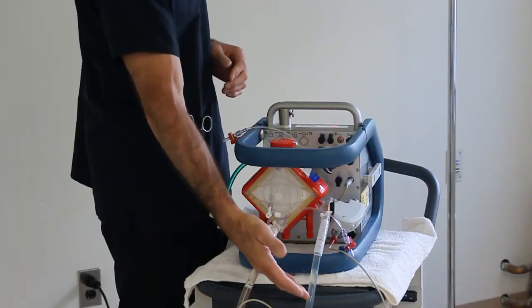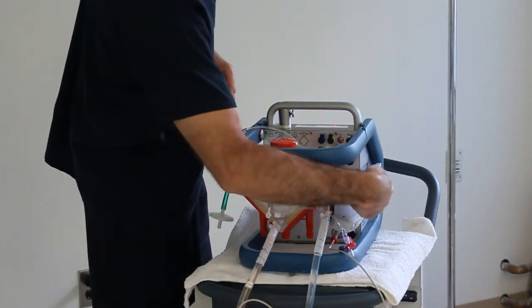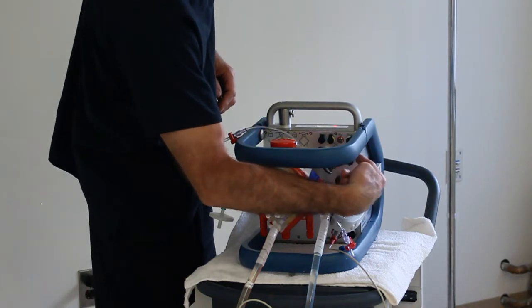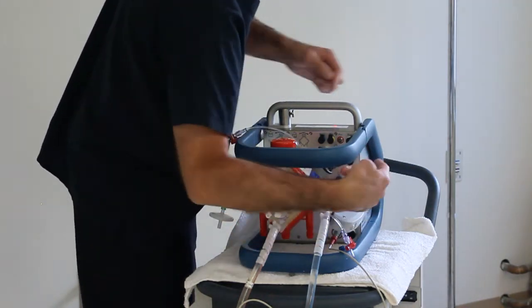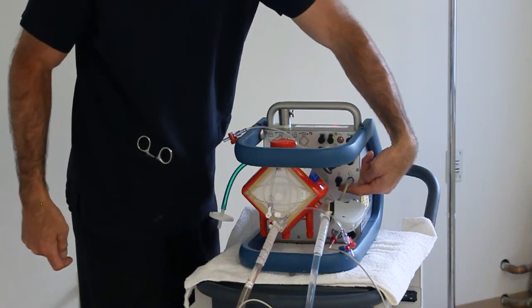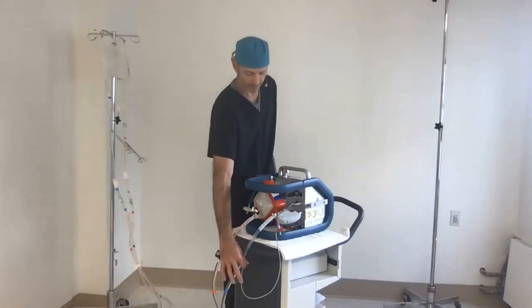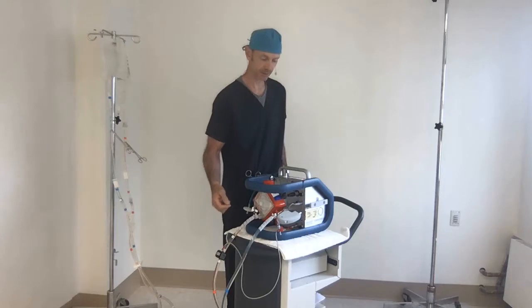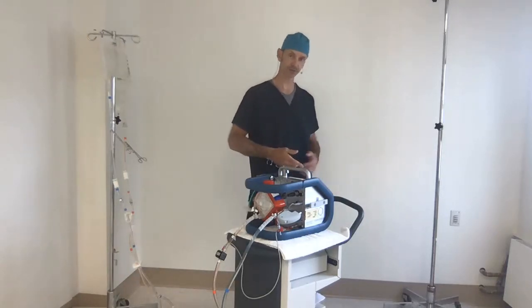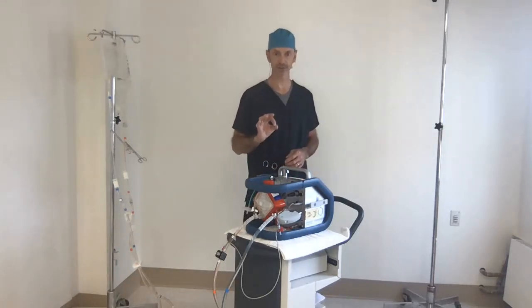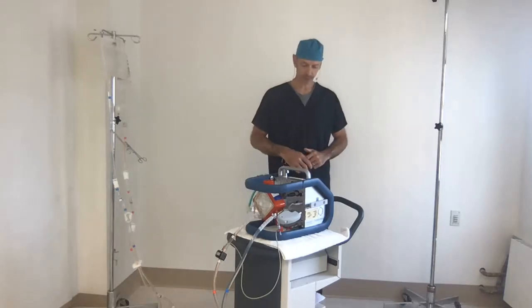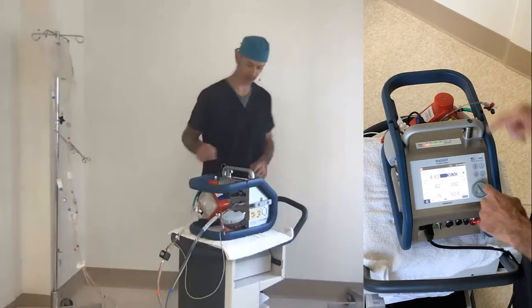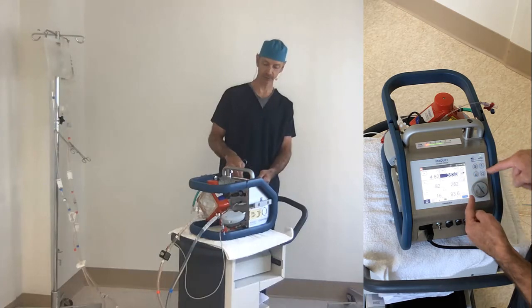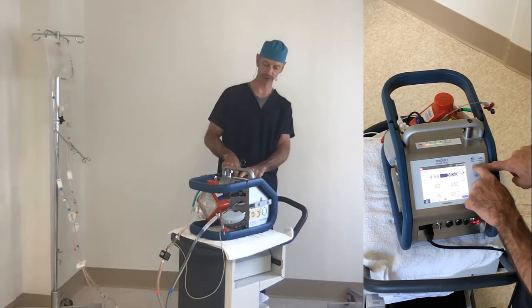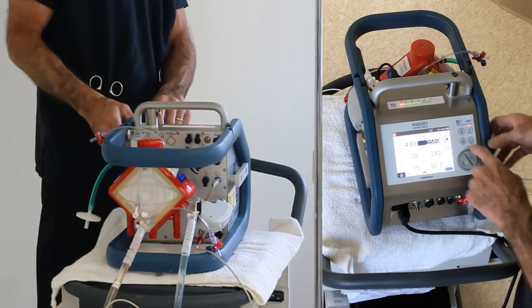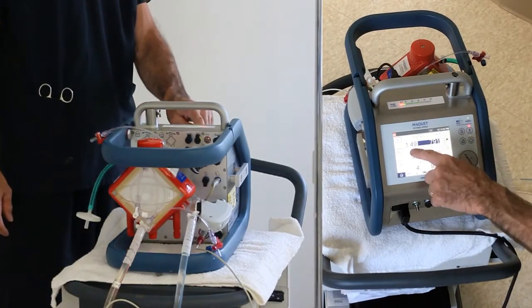So bubbles on the venous side will be hooked up to your venous bubble probe detector, which is this one right here next to the sat/crit. If you have a venous-sided bubble detector hooked up there, you can turn on an intervention. That intervention is called zero flow mode. Zero flow mode, if bubbles came down the line, would look like this. I can simulate that for you by pushing the S button and pushing this 0. And now it goes into zero flow mode. Watch, the flow is going to drop to 0.